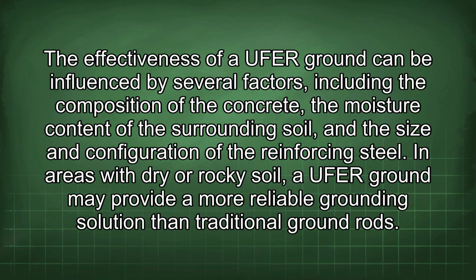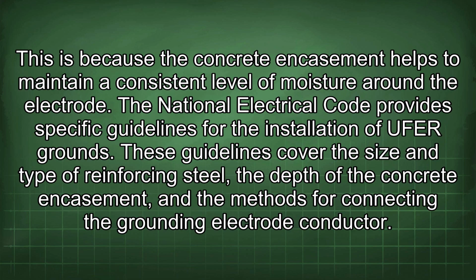The effectiveness of a UFER ground can be influenced by several factors, including the composition of the concrete, the moisture content of the surrounding soil, and the size and configuration of the reinforcing steel. In areas with dry or rocky soil, a UFER ground may provide a more reliable grounding solution than traditional ground rods. This is because the concrete encasement helps to maintain a consistent level of moisture around the electrode.